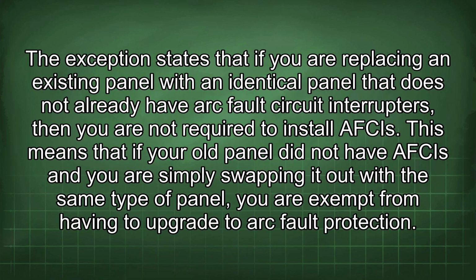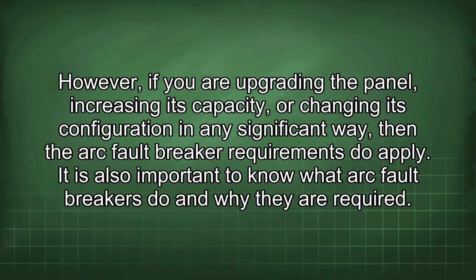The exception states that if you are replacing an existing panel with an identical panel that does not already have arc fault circuit interrupters, then you are not required to install AFCIs. This means that if your old panel did not have AFCIs and you are simply swapping it out with the same type of panel, you are exempt from having to upgrade to arc fault protection. However, if you are upgrading the panel, increasing its capacity, or changing its configuration in any significant way, then the arc fault breaker requirements do apply.